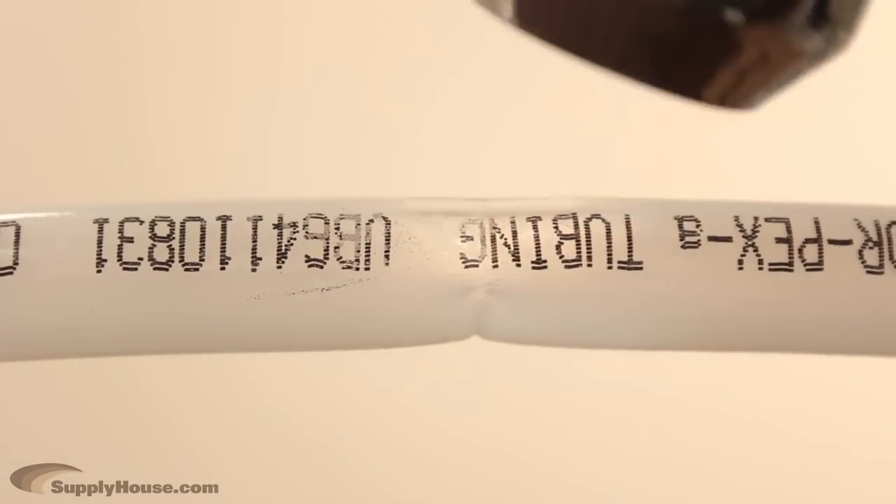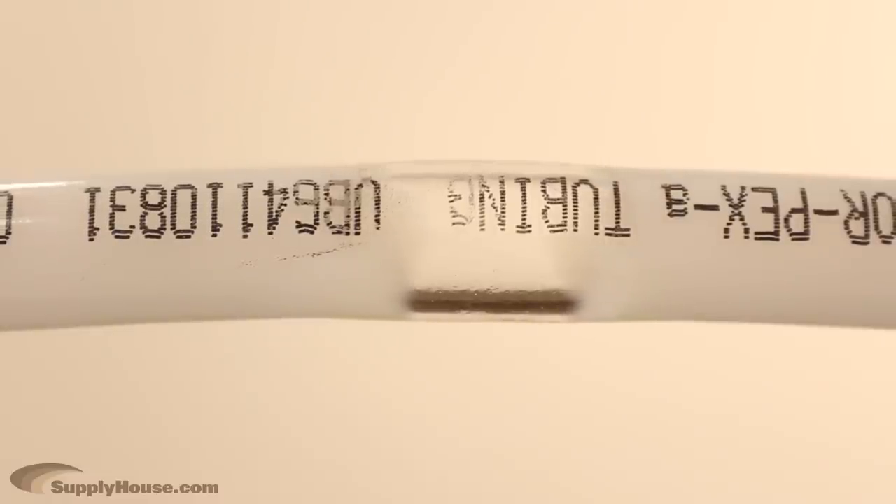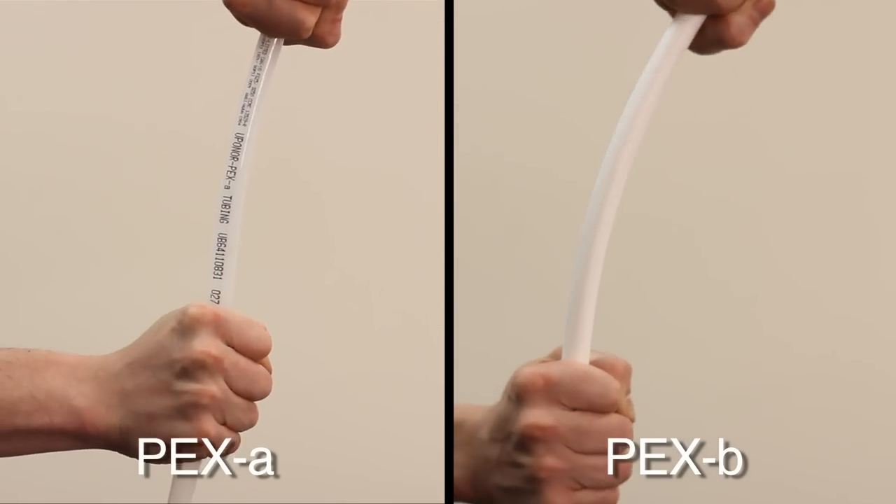PEX-a tubing has thermal memory. This means you can repair any kinks in the tubing by applying heat, and the tubing will return to its original form. It also has greater freeze resistance since it is more flexible than other grades.